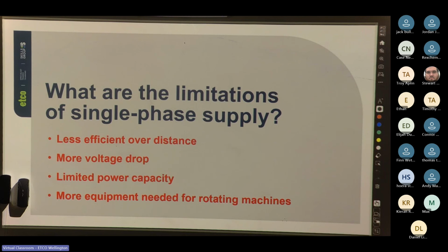If any of you have worked with motors, you'll know that a lot of single-phase motors require extra equipment, whether that be capacitors or other special means of making them operate at single phase. Or we have to use a specialty variable speed drive that takes our 230, converts it into DC, converts that DC into three-phase, and then we can run our motor, which obviously is not very efficient.